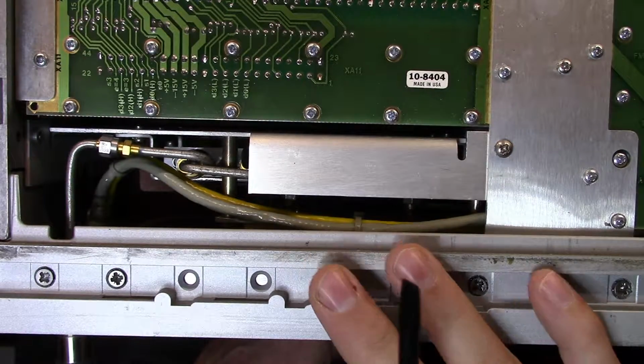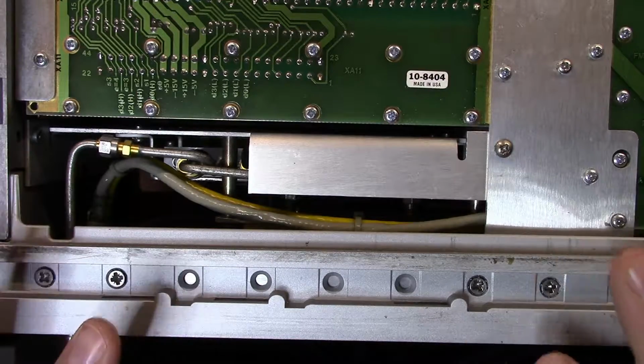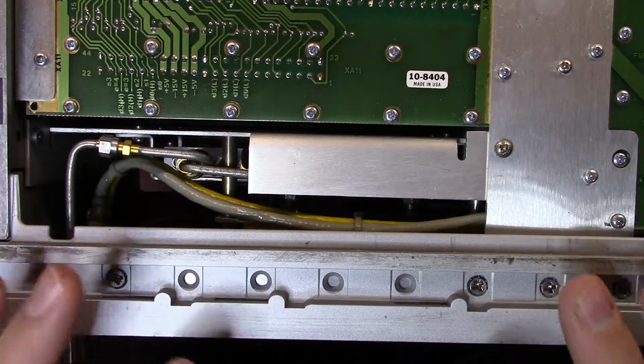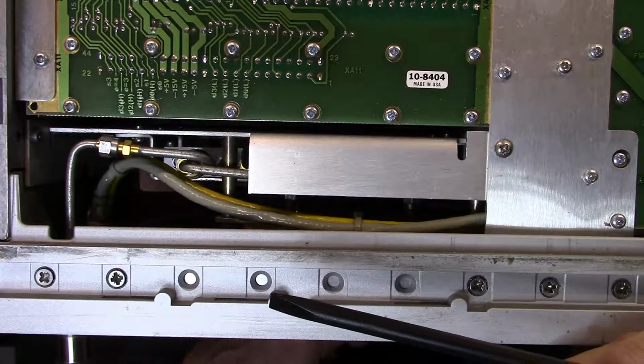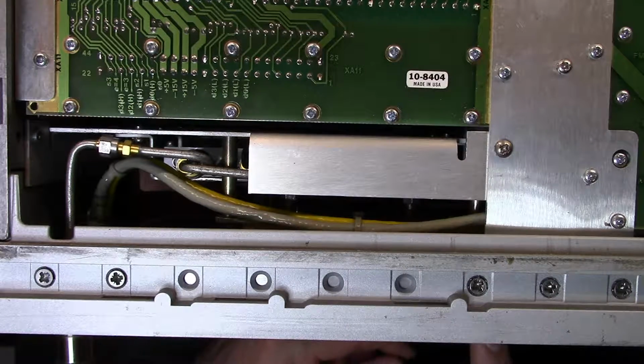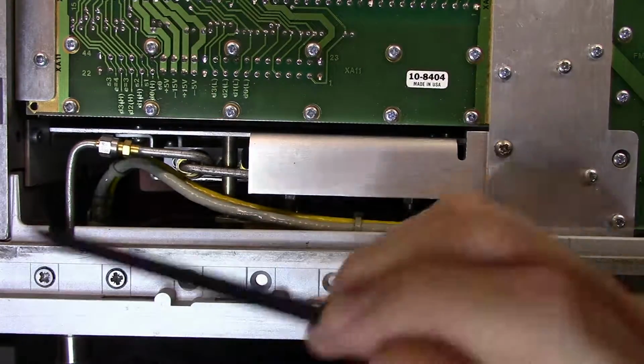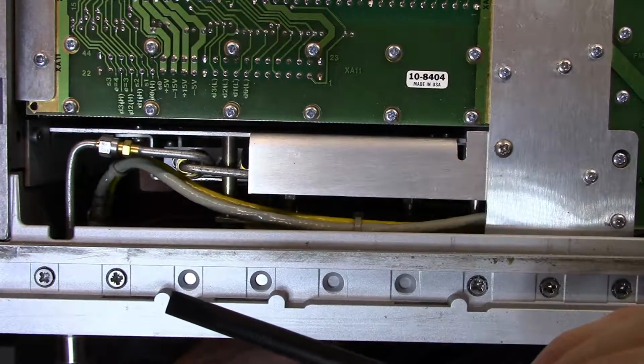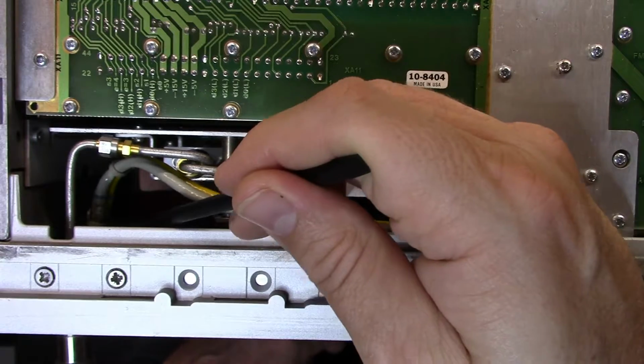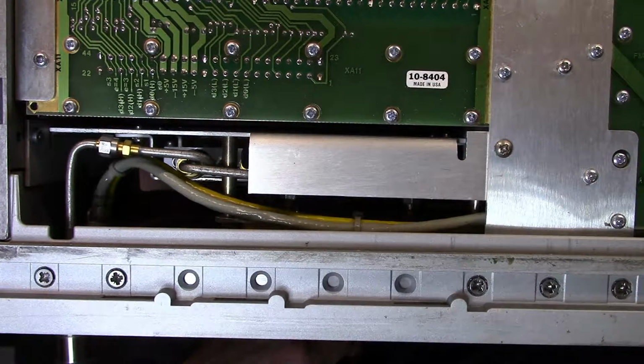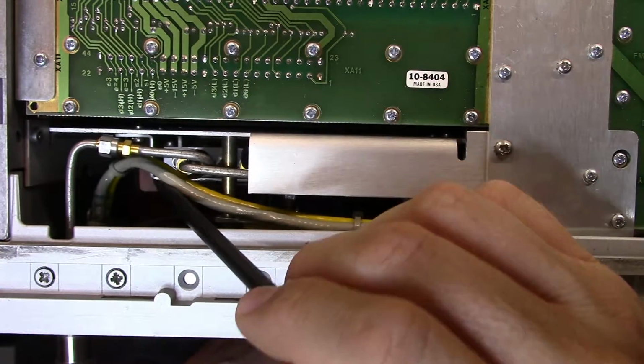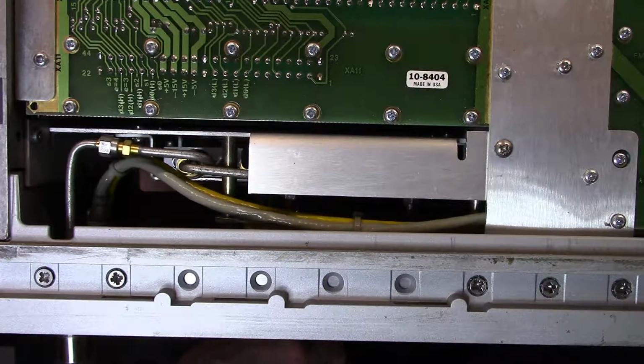Now, when I first got the unit, there was a problem with it in that on the standalone tuned RF, the uncalibrated tuned RF, it would read 10 dB low. And basically, when you use the uncalibrated one, you select RF level and it reads the RF power from the actual RF input here. Whereas if you're using the calibrated one, what it does is just down here on this little set of wires, this goes to a sensor, which is the 11730 cable sensor.